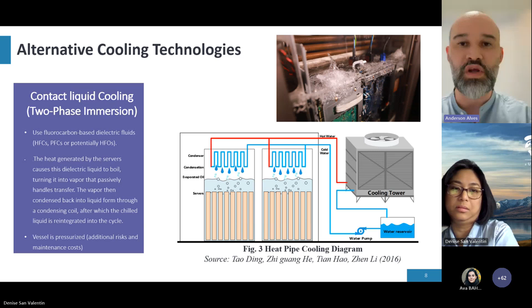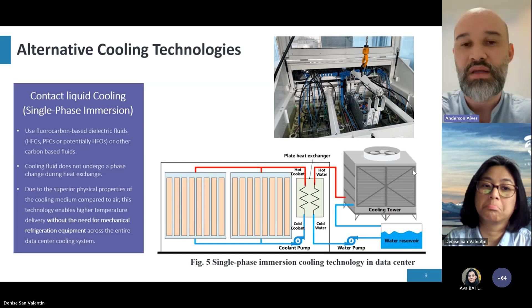And the last technology would be the single phase immersion, which was the technology proposed by the project in China. Basically, you remove the pressurized vessel. You just have one single normal container where you immerse the racks, the servers, and then you have this dielectric fluid that is responsible for cooling down the system. As there is no evaporation, the liquid just continues to run through a condensing unit between cold and hot cycles, cooled down by a water cooling tower outside the unit. So in theory, you could reach much more energy efficiency with fewer drawbacks in terms of the technology's applicability. For example, no use of HFCs or PFCs, and there is no pressurized vessel inside the data center.